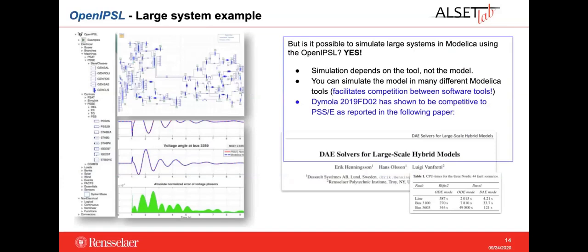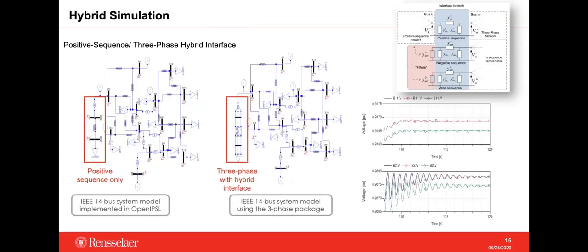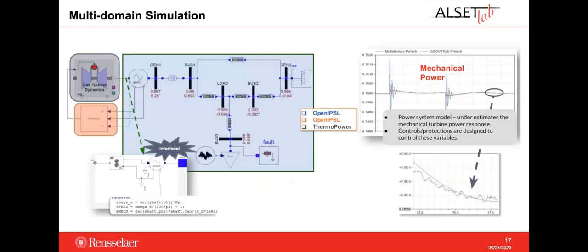The first application is that the library now has a dedicated sub-package of models for the representation of three-phase elements, and an interface model that allows their interconnection to positive-sequence elements. This allows accurate representation of the effects of unbalances in the grid. This study was conducted to show how unbalanced conditions can harm system stability and how you can represent those unbalances using the three-phase package in OpenIPSL.